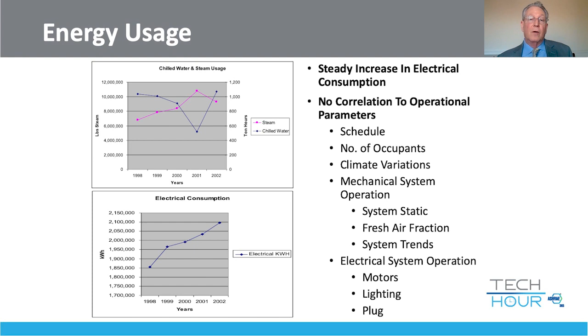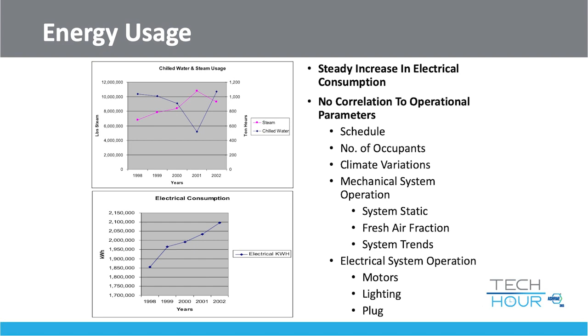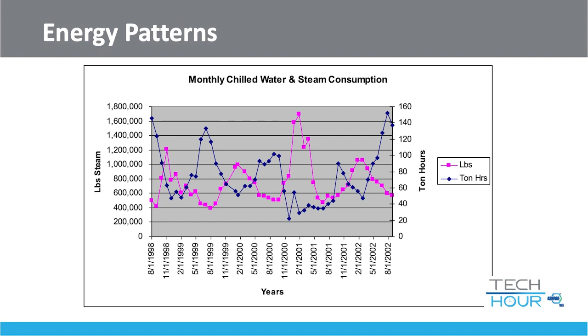Over time, the degradation in building performance created a steady increase in energy consumption. You can see 400,000 pounds of steam consumed in August in Atlanta, Georgia, which has very warm outside temperatures—a clear clue, when you look at energy consumption and the time of year it's used, that there's a problem needing attention. The HVAC systems were consuming 50% more energy than required, due to simultaneous heating and cooling, negative pressurization, makeup air restrictions, and VFDs operating at higher than necessary static pressure. Overall utility consumption was estimated at 40% more than it needed to be.